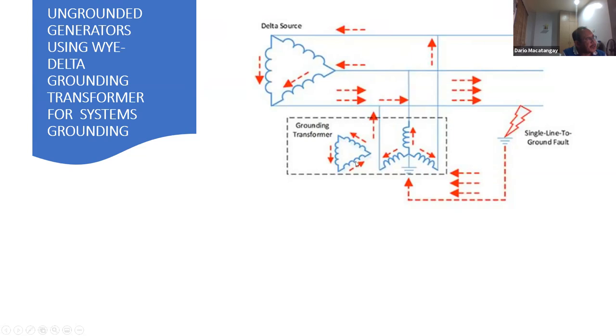In order for this to happen, you need that delta to balance the magnetizing ampere turns on this Y side by the magnetizing ampere turns on the delta side. Without this delta, this current cannot circulate. So it needs to be a delta in a Y-grounded. That's how it's implemented using a grounding transformer. So even if your generator is ungrounded, you can still have a grounding system if you have a grounding transformer.